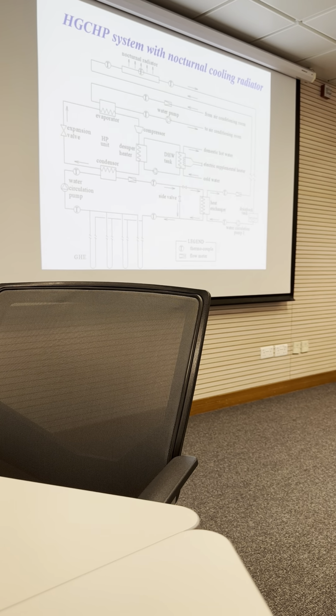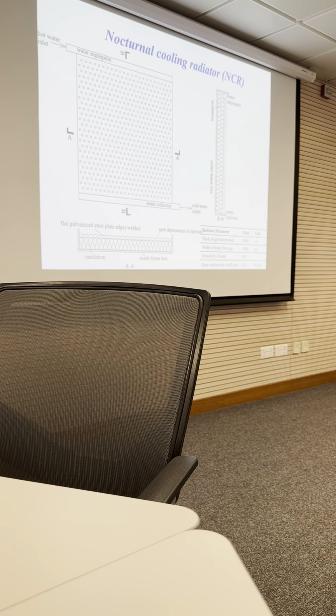So we can use this technology to cool the condenser. Then we can reduce the amount of energy inject into the ground by the ground heat exchanger. This is also very useful, very effective. This is the structure of nocturnal cooling radiator. That's a heat exchange between the fluid in the condenser and the outside air or sky.